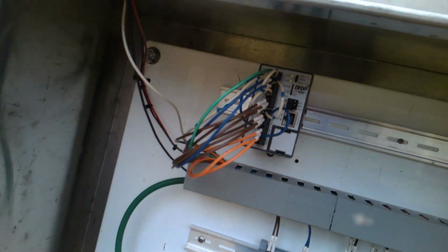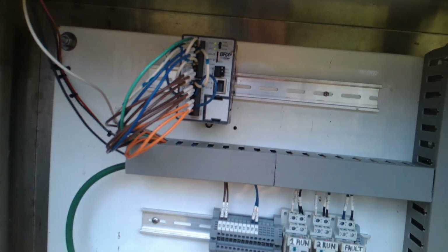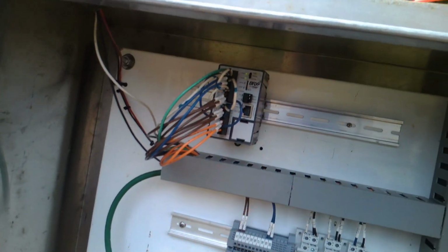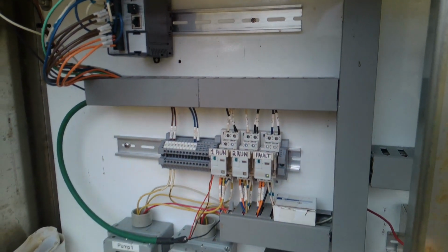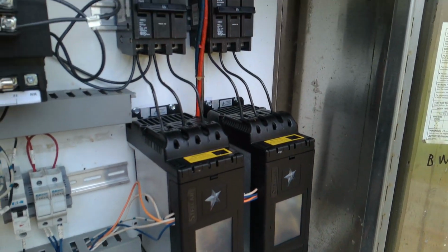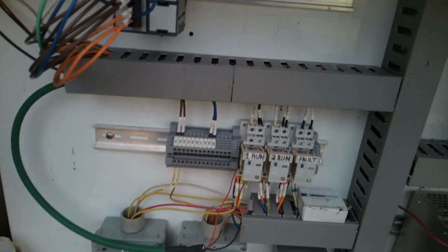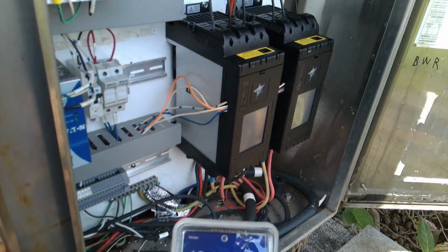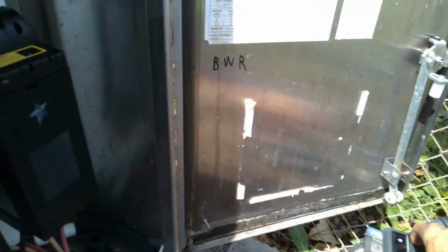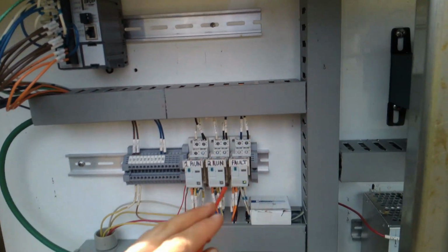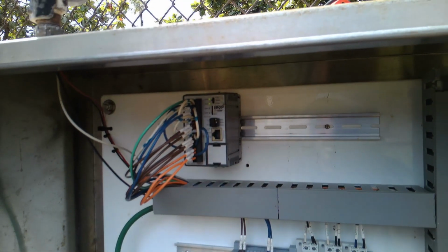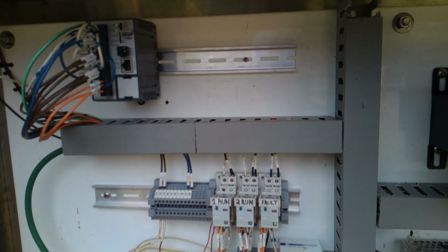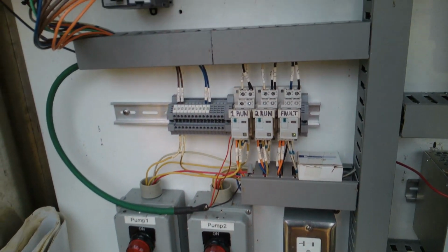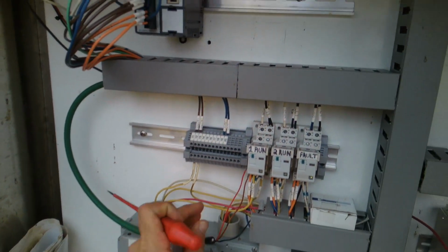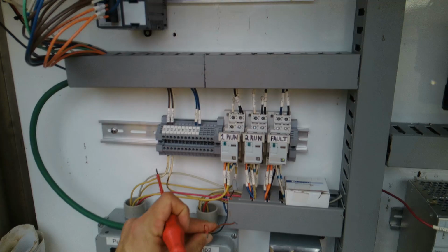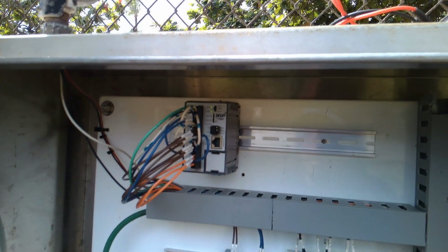So now we're in a transducer fault. Y2 is the strobe. So the fault we're in now is a transducer failure. I wonder if the transducer level is fluctuating so much that it's calling for 1, it's calling for 2. That could be it. I think it'd be worth it to actually get my milliamp tester out and just see this analog signal raw with my tester.